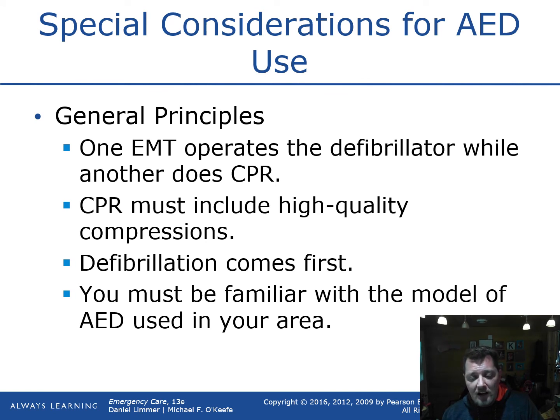So if an establishment like the library has AEDs in each of their facilities, and they have a LifePak type AED, same manufacturer, we can take out their connection from their AED and plug it right into our monitor without having to take the pads off and switch the pads out.